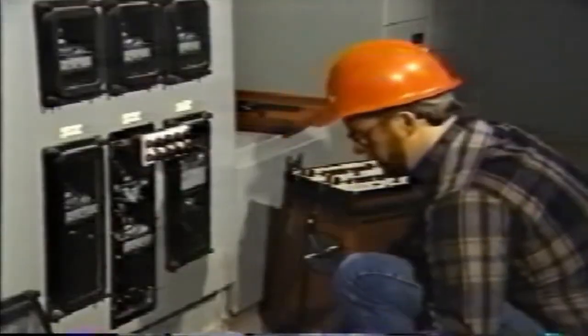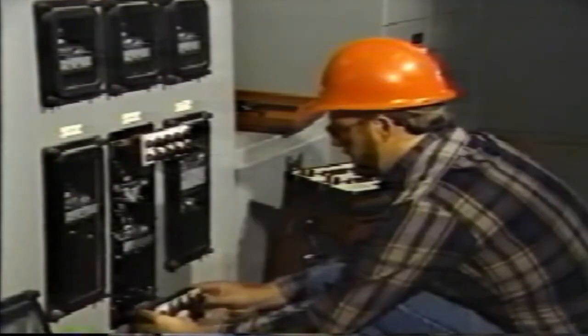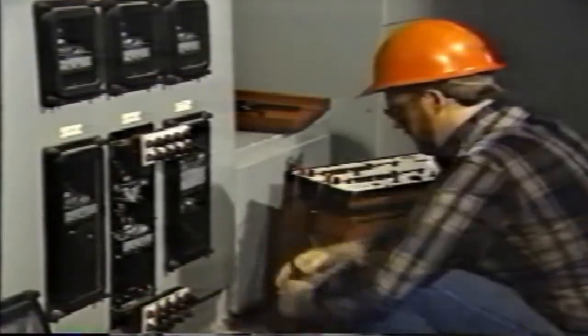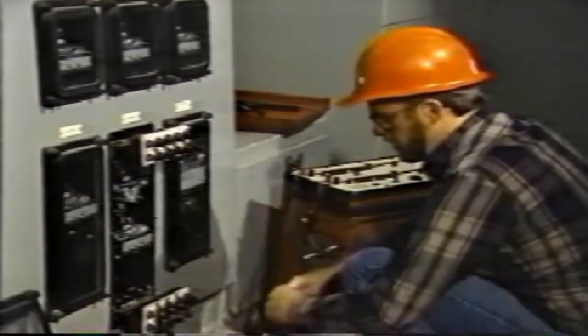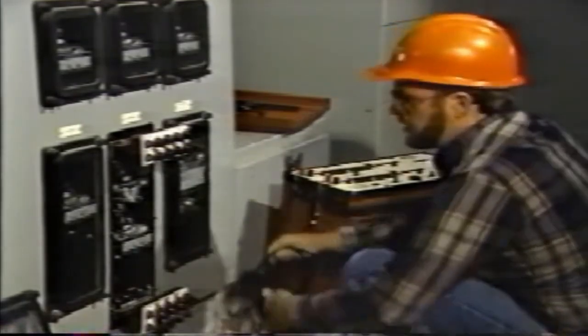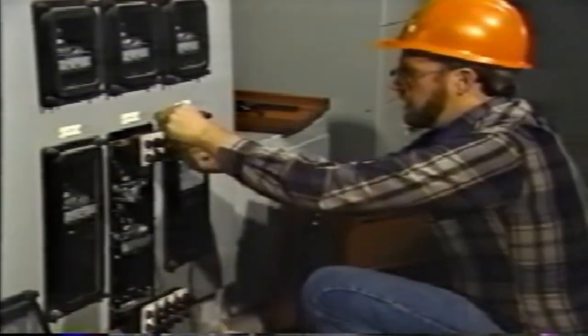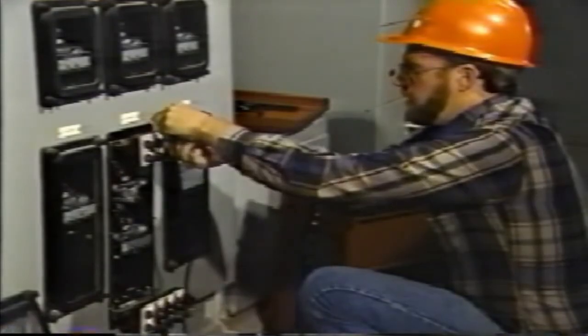We can all help with this. Maintenance outages should be kept as short as possible so that equipment is returned to service within the minimum time period. If any testing is to be carried out on live equipment, for example, protection schemes, the system operator must be fully informed of the activity so that he can take precautions against any possible mishap.